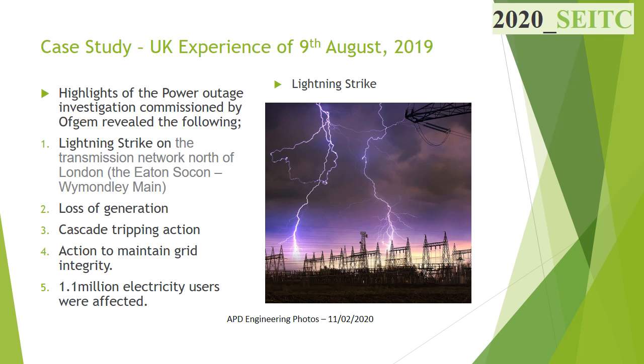The action of the LFDD, backed by dispatch of additional generation, returned the system to normalcy. Disconnected customers were fully reconnected to supply by the distribution network operators by 5:37 p.m. In all, the whole event lasted about 45 minutes for full power restoration to be achieved.